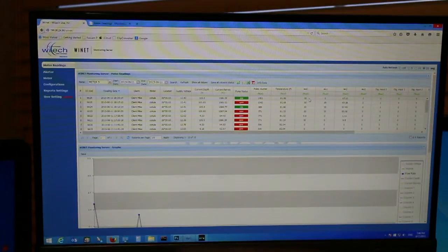Okay, but analog input 0 is used if you hook this up here and you measure this, it's going to show you from 0 to 50 in this case, because I have set up in the unit that the 0 and span is 0 and 50. Okay, 4 and 20 milliamps, it's 0 and 50, whatever, 50 feet, 50 psi, whatever. Okay, and that's what I'm going to see here.